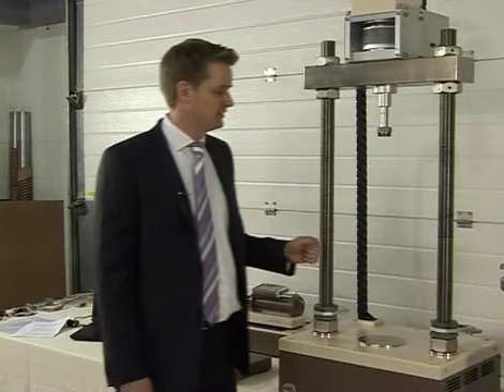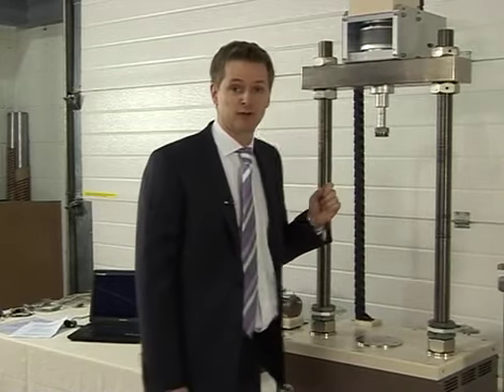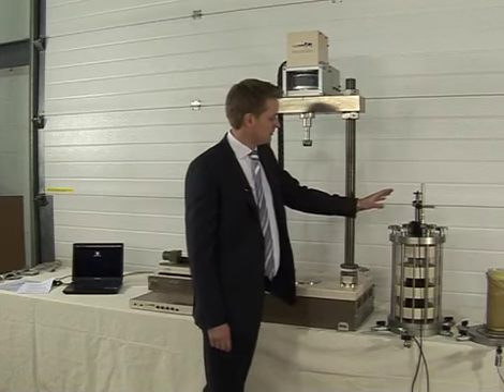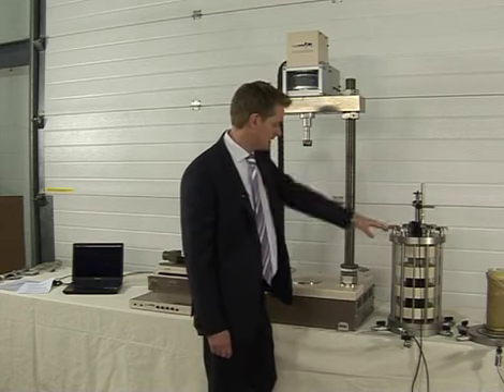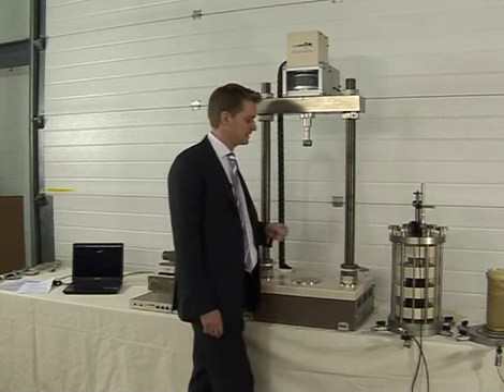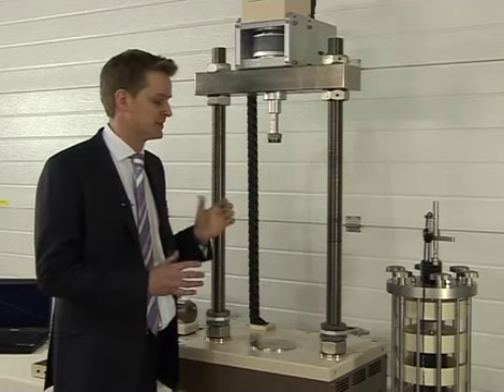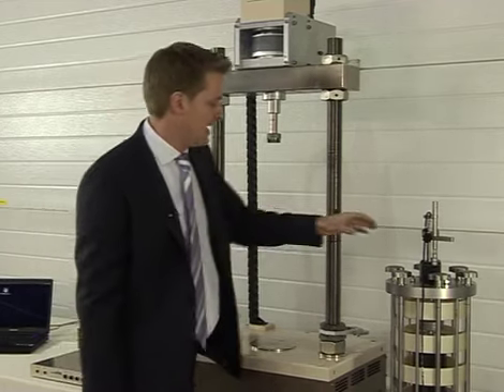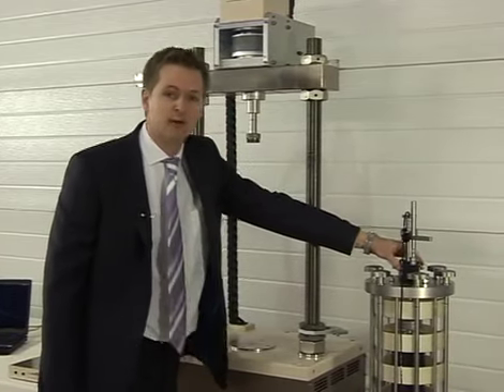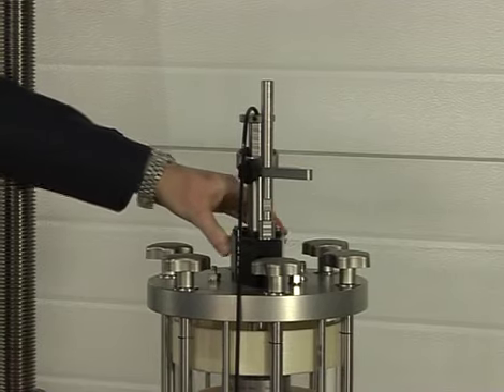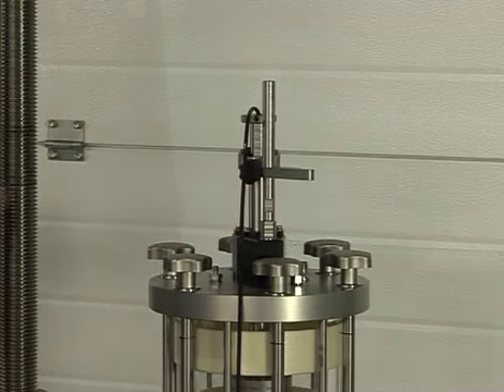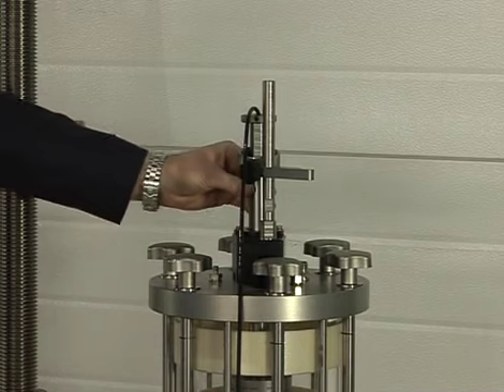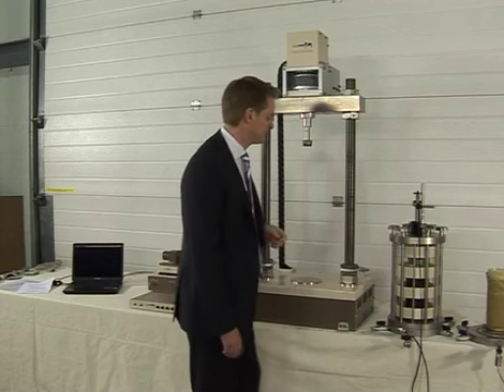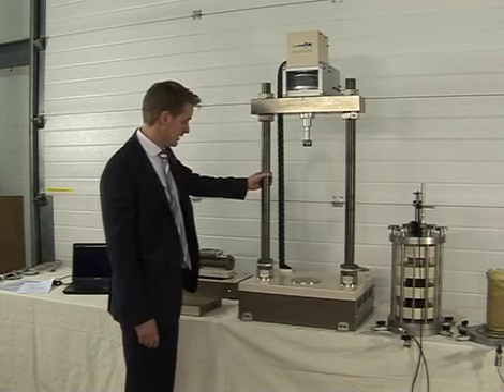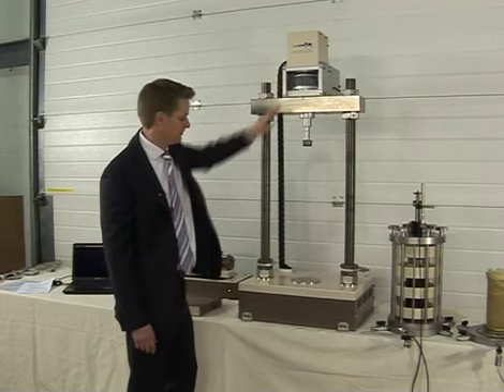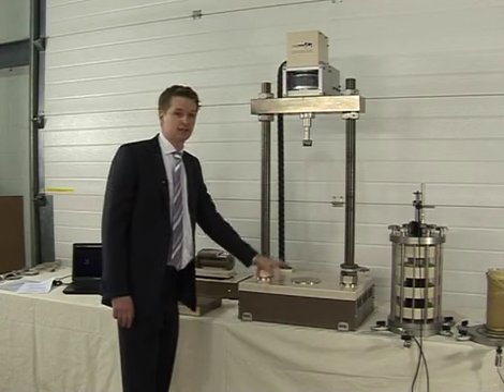The basic configuration of the ELDYN system, and the example I'm going to show you today, is made up of a triaxial cell. This one is a GDS 100mm triaxial cell for samples up to 100mm diameter, 200mm height. It has a dynamic upgrade, which is a linear bearing that holds the ram laterally stiff and reduces the friction during the dynamic testing. The ELDYN load frame has the actuator at the top, and the drives and the electronics in the base of the system.